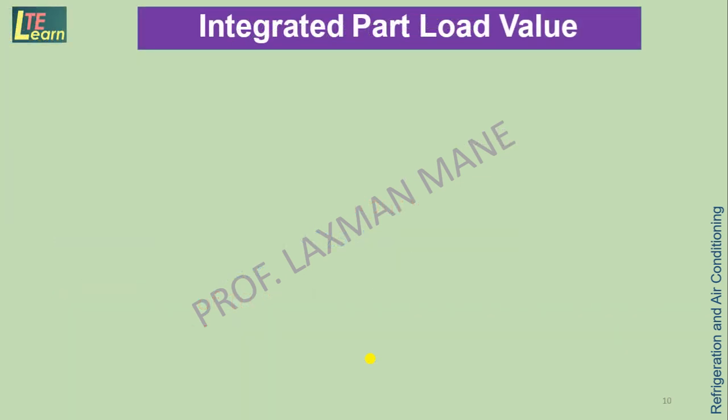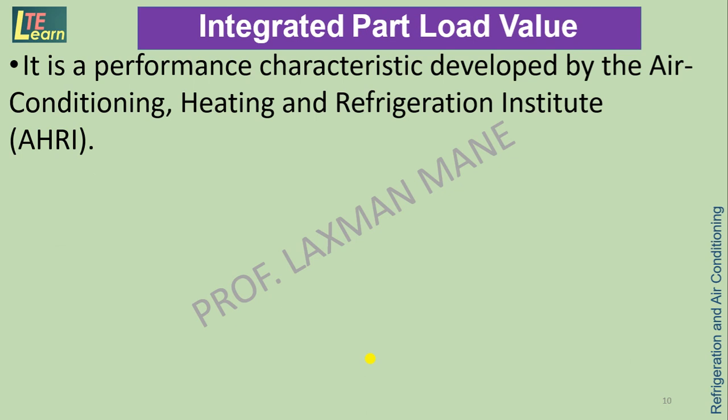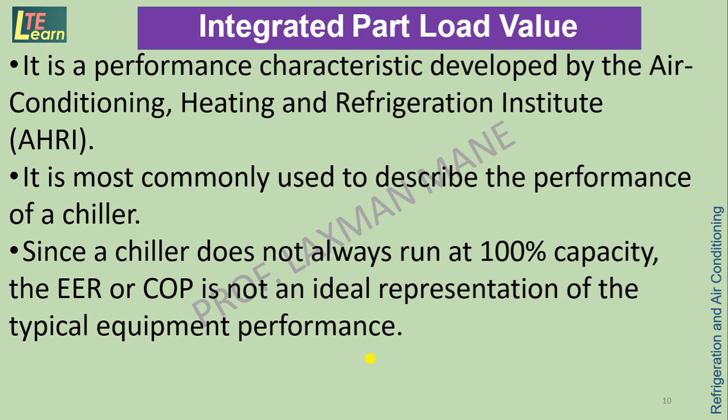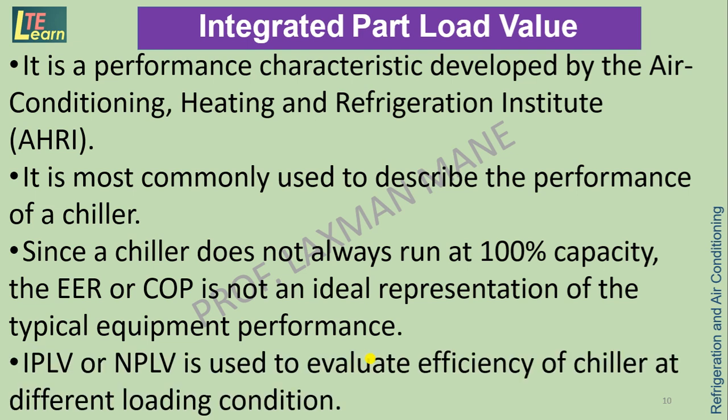Integrated part load value. It is a performance characteristic developed by the Air Conditioning, Heating and Refrigeration Institute, that is AHRI. It is most commonly used to describe the performance of a chiller. Since a chiller does not always run at 100% capacity, the EER or COP is not an ideal representation of the typical equipment performance. So IPLV or NPLV is used to evaluate the efficiency of a chiller at different loading conditions.